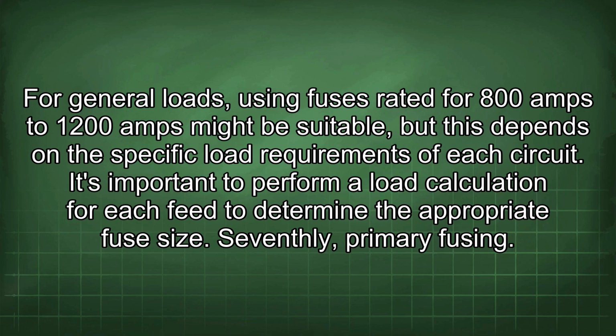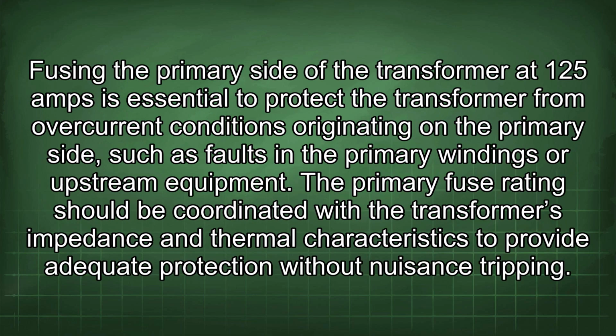Seventhly, primary fusing. Fusing the primary side of the transformer at 125 amps is essential to protect the transformer from overcurrent conditions originating on the primary side, such as faults in the primary windings or upstream equipment. The primary fuse rating should be coordinated with the transformer's impedance and thermal characteristics to provide adequate protection without nuisance tripping.